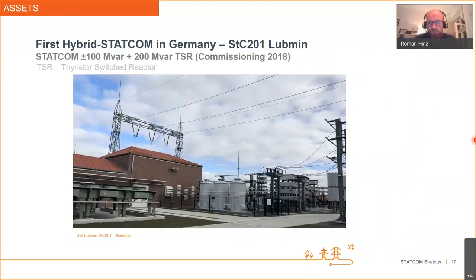So as my colleagues already explained, we are facing several problems in 50Hertz, especially for voltage angle jumps, also for steady state voltage changes, also for dynamic voltage changes. Fortunately, the solution will be the STATCOM, and fortunately, we have some experience already with STATCOMs. For example, in Germany, we have installed with Siemens together the first hybrid STATCOM, which is located in the north of Germany, and this is more or less an offshore STATCOM, because when there is a fault ride-through contingency in our offshore grid, this STATCOM will react immediately and will inject inductive reactive power immediately together with a thyristor switched reactor.